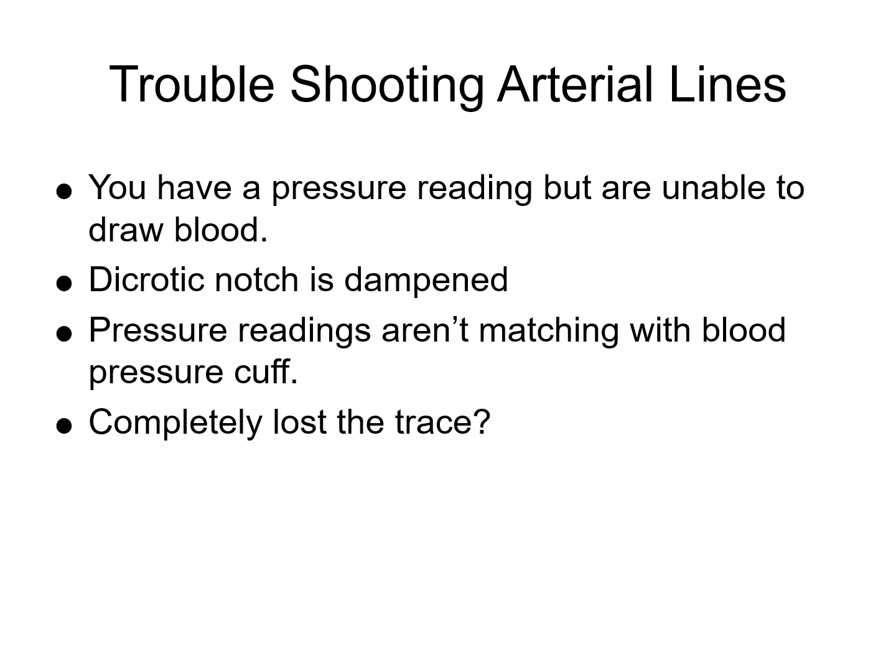Alright, if you have a dampened dicrotic notch, like it's completely gone, it could be an air bubble in the transducer.